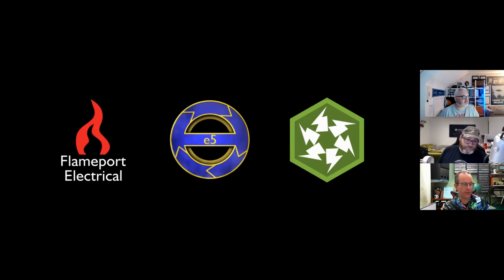What it says is that in island mode, the PEI is disconnected from the public distribution network. Therefore, the system earthing of the PEI may differ, and the switching device suitable for that shall disconnect all live conductors from the public distribution network. So it doesn't say that it has to disconnect the earth as well. However, it doesn't say that it doesn't either. So it could be disconnected, or it could remain connected. But it has to connect neutral to earth. Yeah, it's connected neutral to earth anyhow, and if it goes into a TT system.